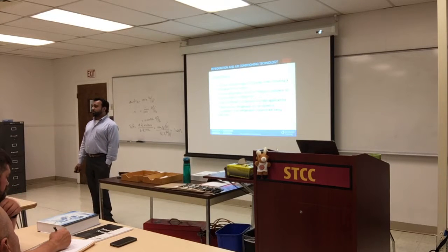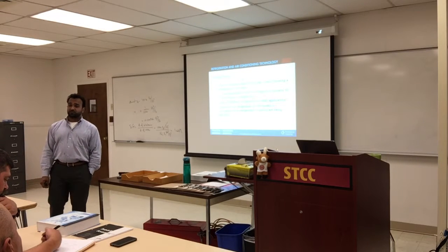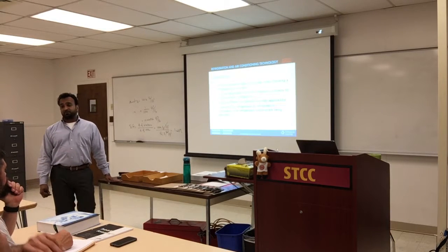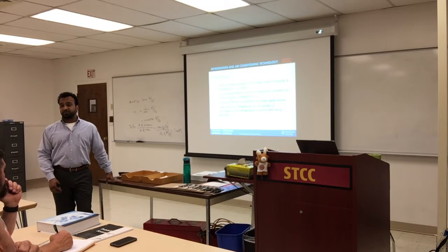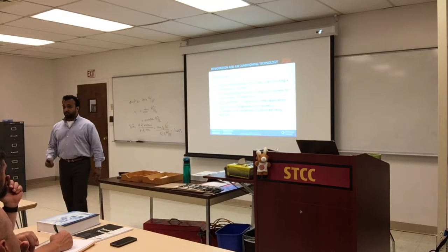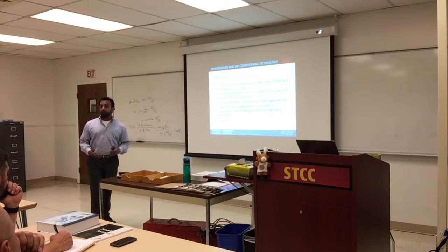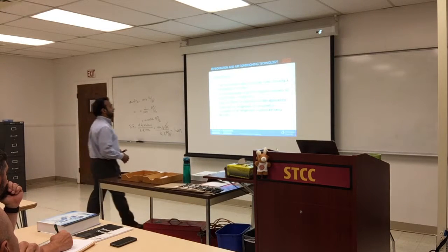Colors. Refrigerants are not to be mixed. They are pre-made, manufactured to certain specifications. What happens if you mix them? It will change the properties, right? Every one of them is designed to boil at some temperature and condense at another. If you mix them, you have lowered their properties and the unit might not function the way it's supposed to.